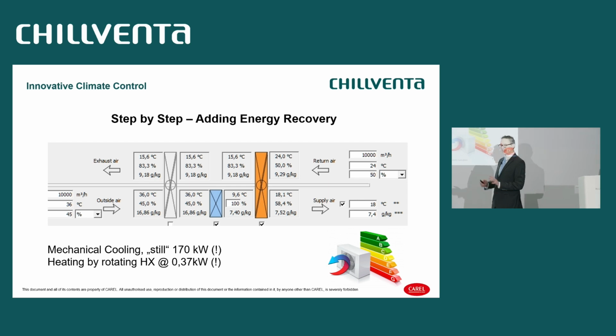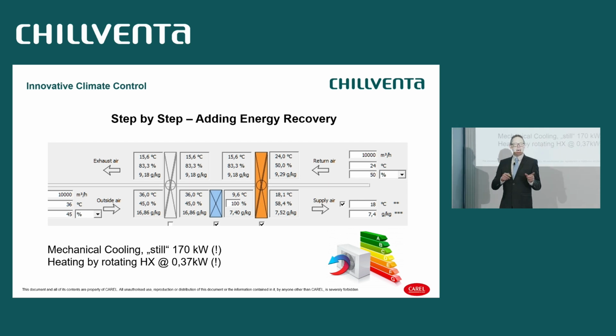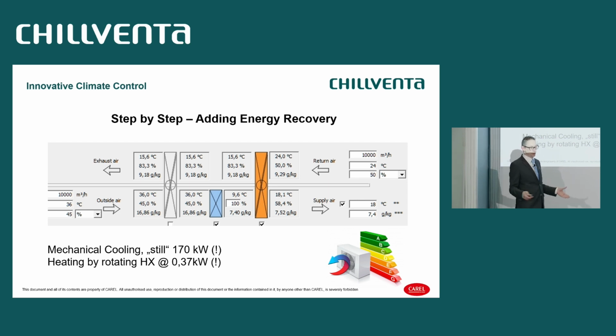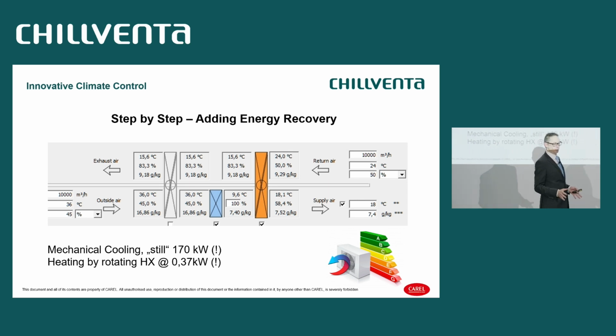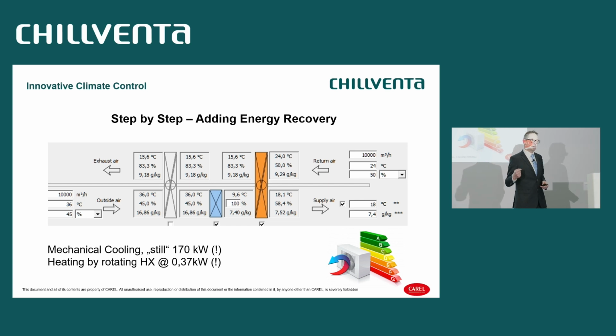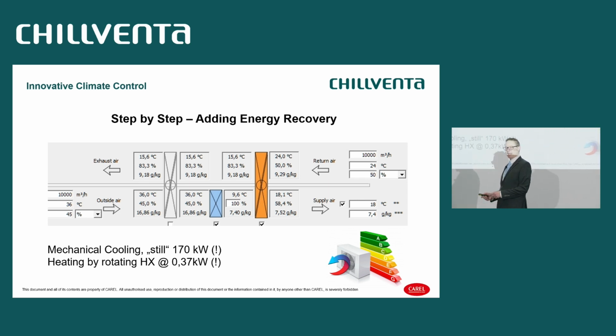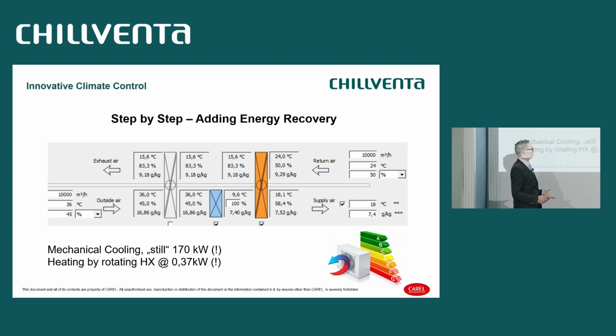So we still have the 170 kilowatts of pure waste energy. I call it waste energy because you will see afterwards, you don't need that much of energy. But what you have now already, by just putting one wheel inside, 28 kilowatts are going down to 0.37 kilowatts. Speaking about 370 watt heating power, that's neglectable, we don't really need to speak about it. And the auxiliary energy, that is the important point to keep in mind, this wheel runs with an auxiliary drive at 180 watts. So you invest 180 watts to save 30 kilowatts. Sounds like a good idea, and it is.